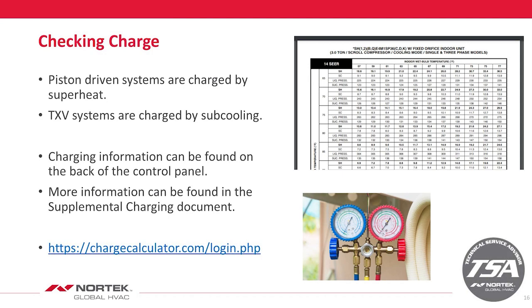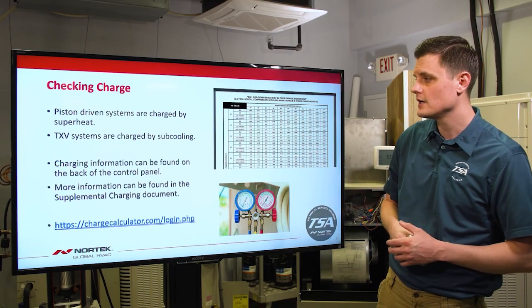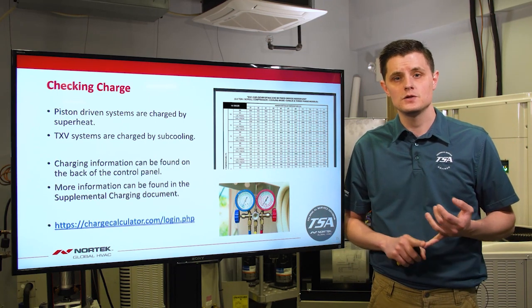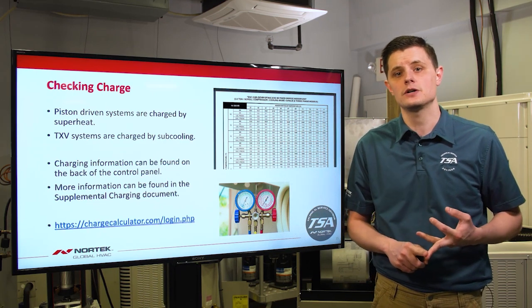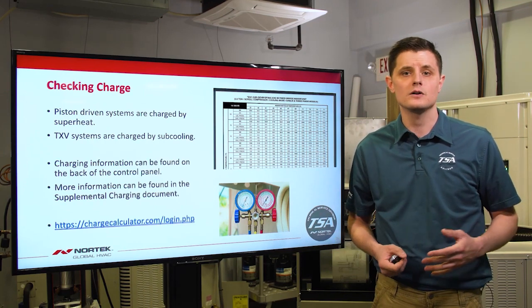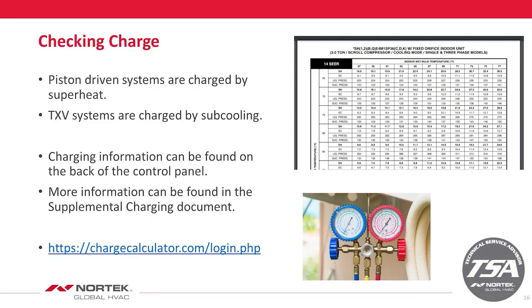The supplemental charging document is available on our technical literature library. It includes high side and low side pressure along with superheat, subcooling, and discharge temperature numbers. That will vary by tonnage and whether you're in cooling or heat pump mode. Another way to check charge is through our charge calculator website at chargecalculator.com, or use the QR code 'charge me' sticker on the outside of the control panel to go directly to that website.